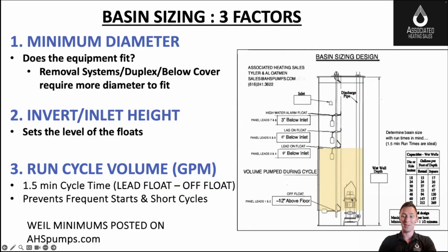We don't have unlimited basin depth is what I'm trying to say. So we can't put in a 15-foot basin and all that. We're typically at around 8 or 9 feet on some of these systems. So we need to understand how much depth we need so that my pump runs for at least a minute and a half. That's going to be a short cycle if it runs for 30 seconds or a minute and turns on very often throughout the hour.